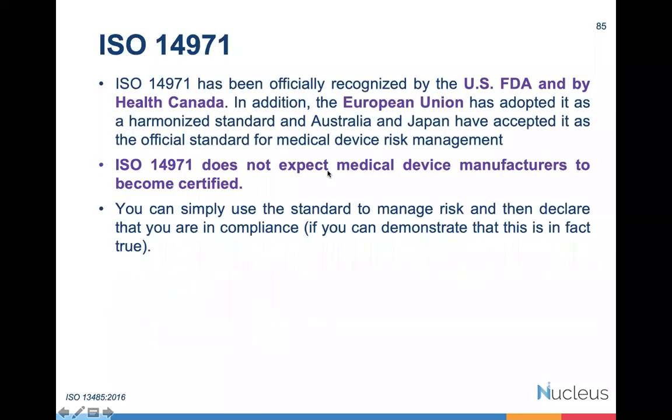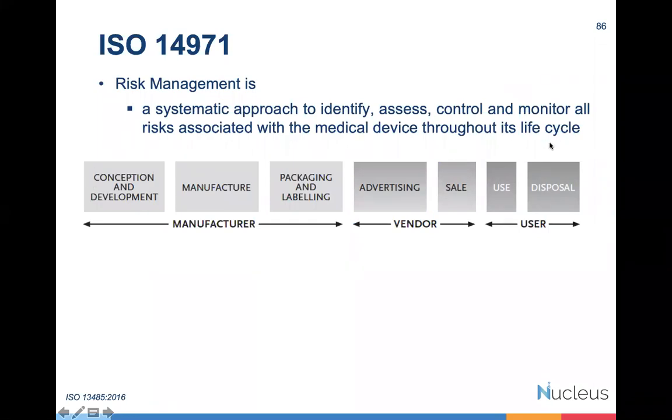Okay, see, US FDA, even Health Canada, and some parts of Europe mandated this approach of risk management. It depends on the role you have. This is not a certifiable standard. It's only a guideline. It tells us how to do your risk management. That's all. The standard gives you a structured outline. The risk management needs to be applied across the entire life cycle.